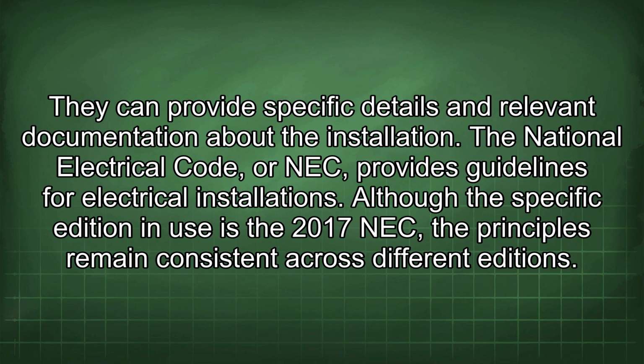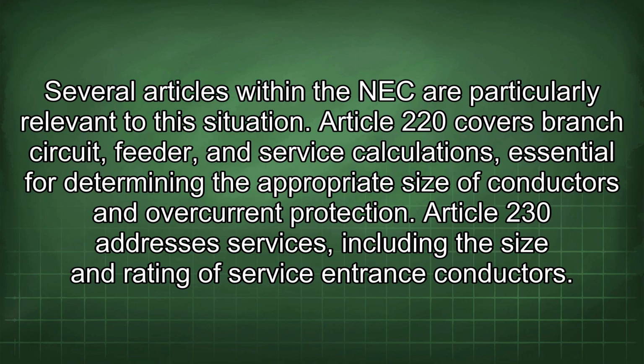The National Electrical Code, or NEC, provides guidelines for electrical installations. Although the specific edition in use is the 2017 NEC, the principles remain consistent across different editions. Several articles within the NEC are particularly relevant to this situation. Article 220 covers branch circuit, feeder, and service calculations, essential for determining the appropriate size of conductors and overcurrent protection. Article 230 addresses services, including the size and rating of service entrance conductors.